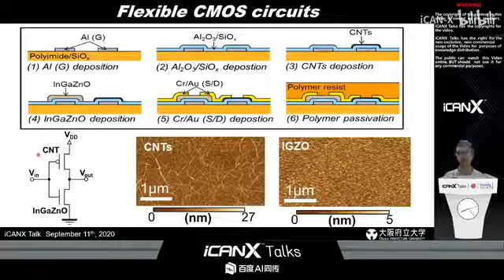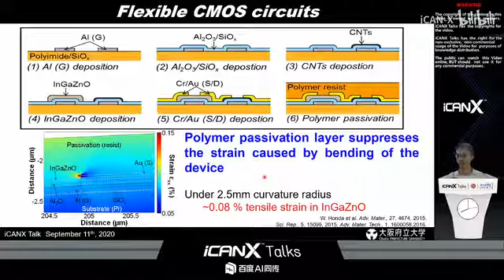So our device structure is like this, the fundamental CMOS structures. The reason why we deposit the polymer as a passivation layer is to suppress the strain caused by the bending of the device, since this is a flexible transistor circuit. By adding the passivation layer, we can reduce the strain to 0.08% under a 2.5 millimeter curvature radius. Of course, if you control the thickness more, we can reduce the tensile strain even more under such a low bending radius.